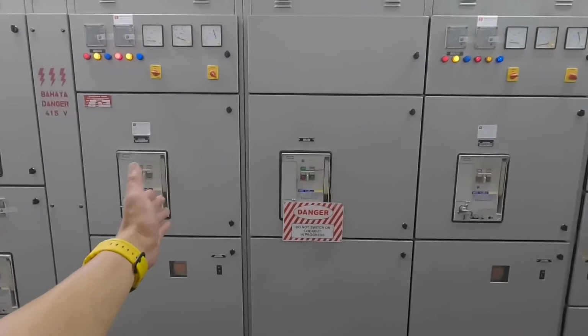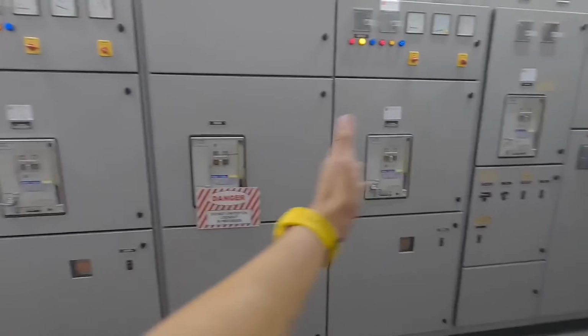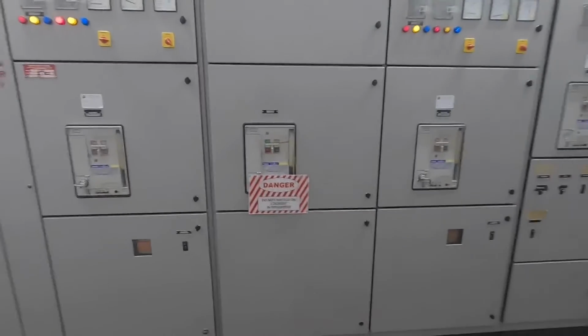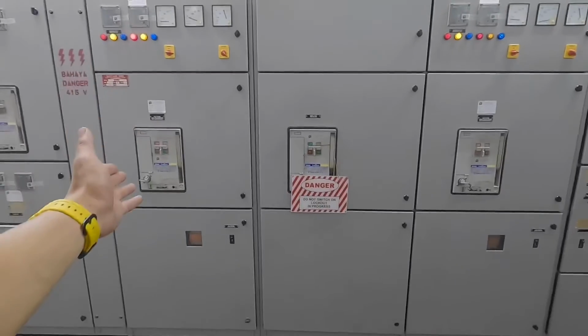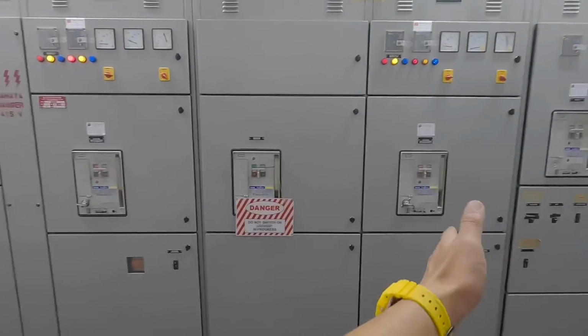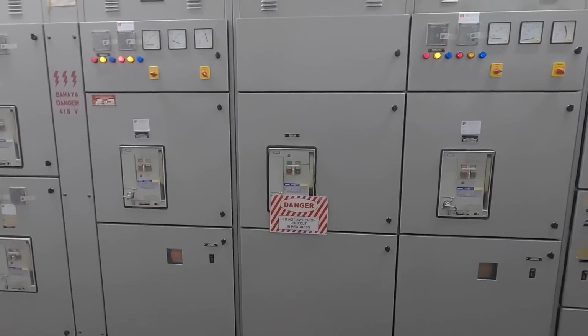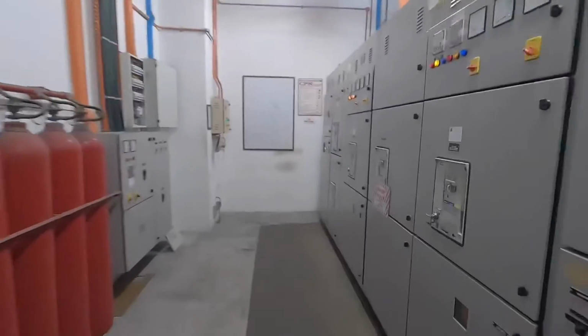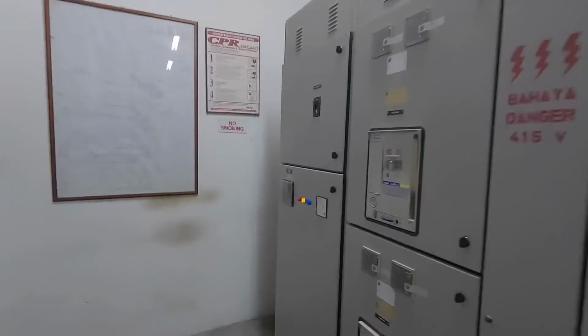This is MSB number 1 bus bar coupler, and this is MSB number 2. If MSB number 1 on and MSB number 2 on, the coupler must be off. Between these three, one must be off. Alright, now as we wait for the genset to stop, let us visually check the switch room. Alright, genset is stopped automatically by itself. Now everything has gone back to normal.